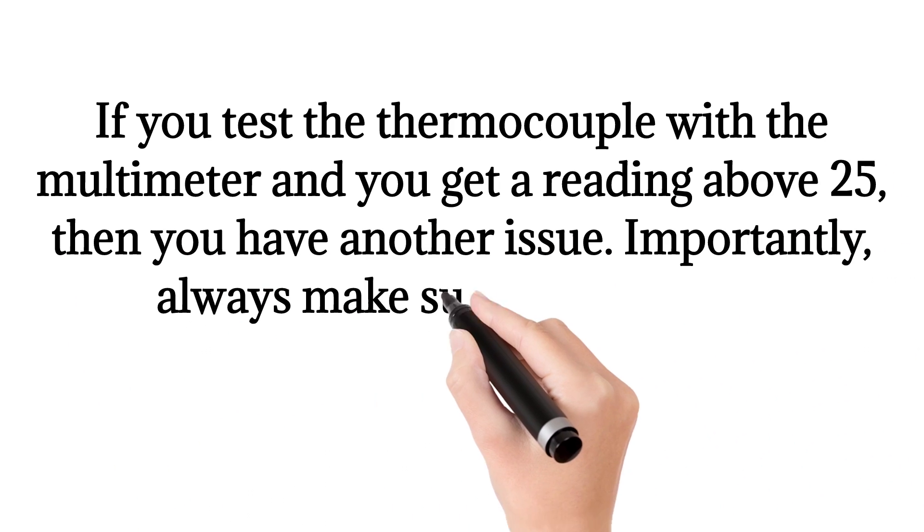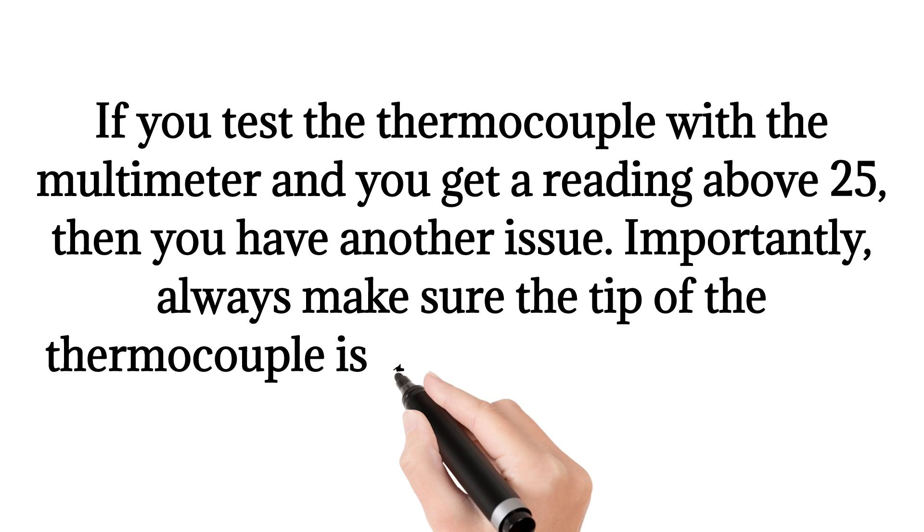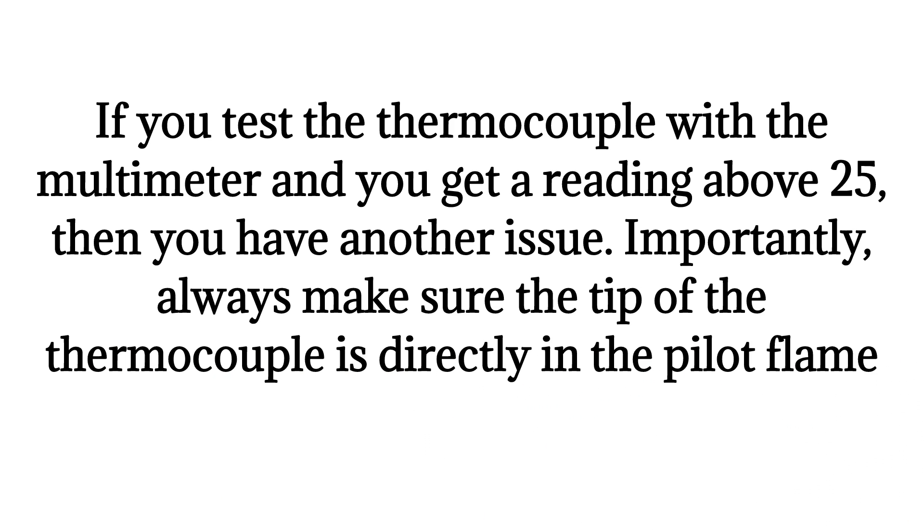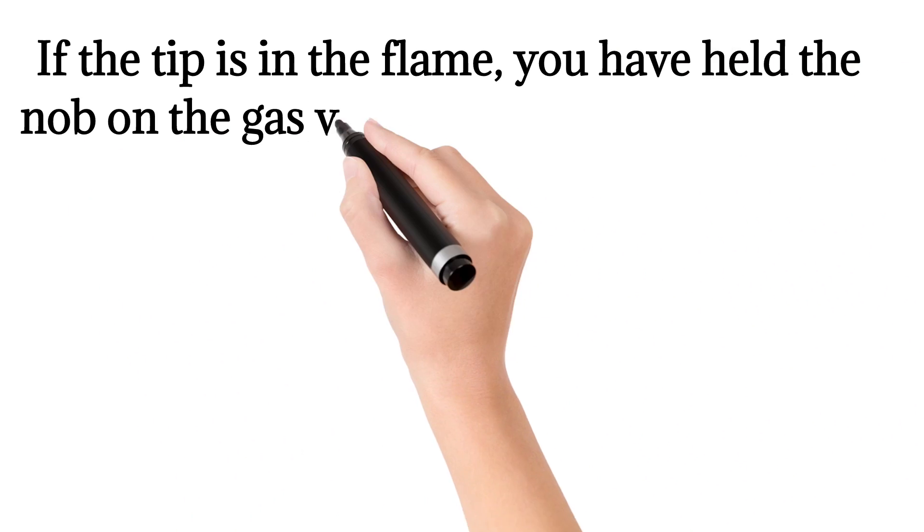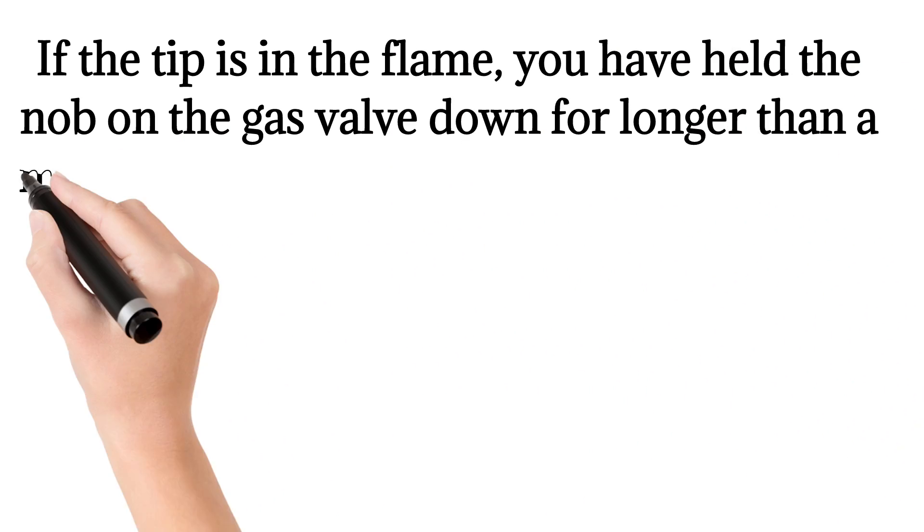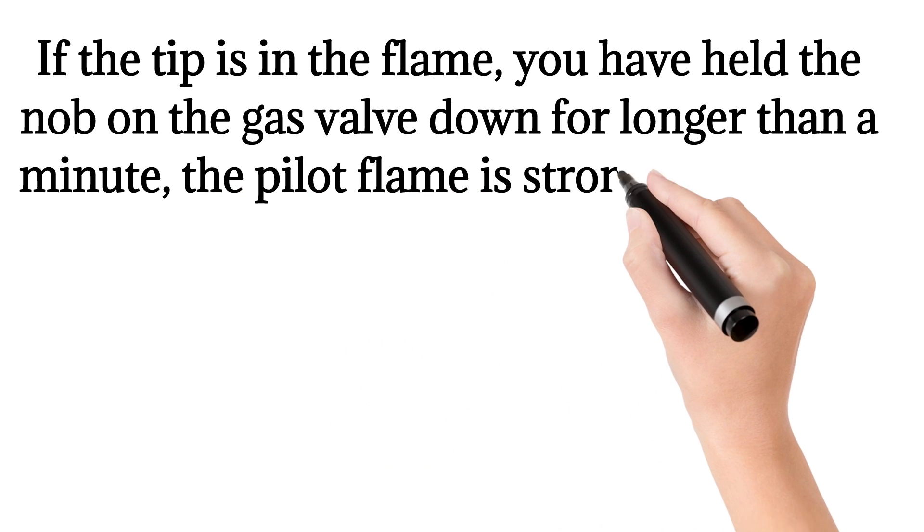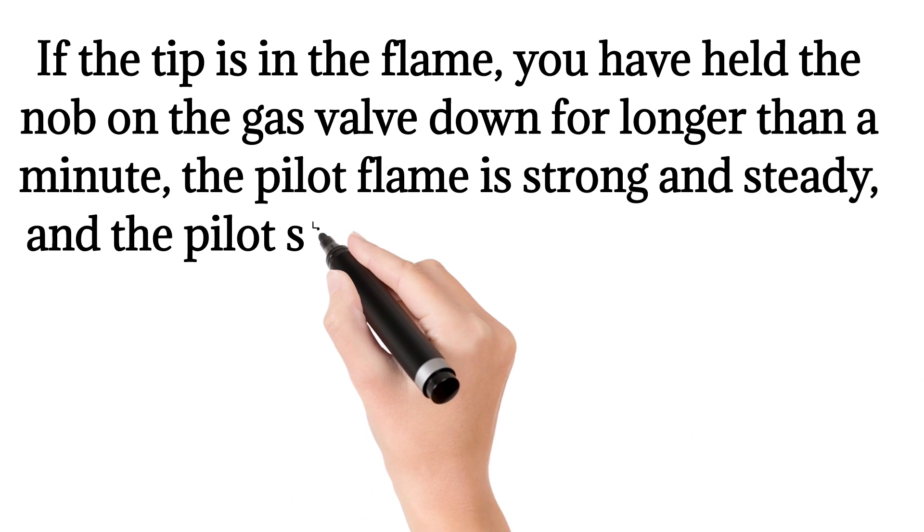Importantly, always make sure the tip of the thermocouple is directly in the pilot flame. If the tip is in the flame, you have held the knob on the gas valve down for longer than a minute, the pilot flame is strong and steady, and the pilot still does not stay lit, then you likely have a problem with the gas valve.